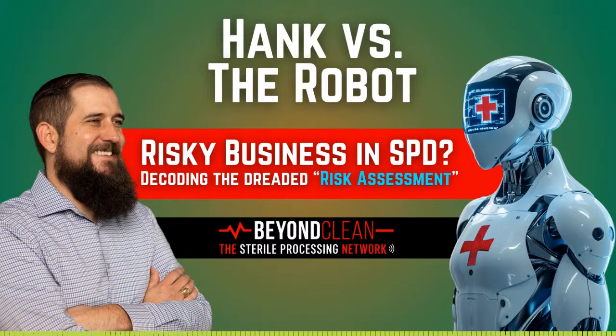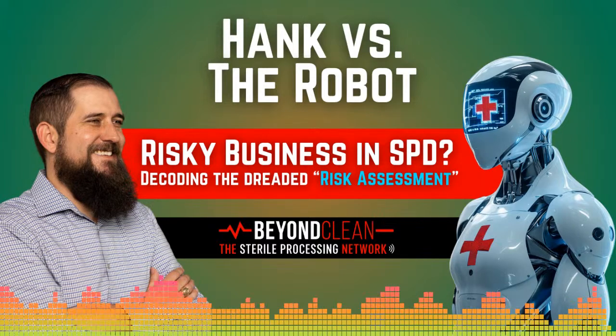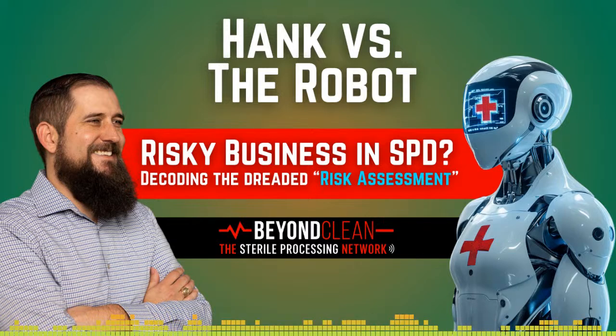One of the key takeaways is that risk assessments aren't just about identifying the problem. They're about systematically analyzing the likelihood and severity of potential outcomes. For example, if you have consistent wet packs, it's not just a machine issue. It's a risk to sterility assurance and surgical site infections. The article also ties risk assessment into compliance, pointing to guidelines like AAMI and how surveyors might approach these scenarios. It's a hands-on approach that aligns well with what we see in real-world sterile processing departments. So it's a solid backdrop for defining what a risk assessment is and why it's so crucial. Where should we go next?